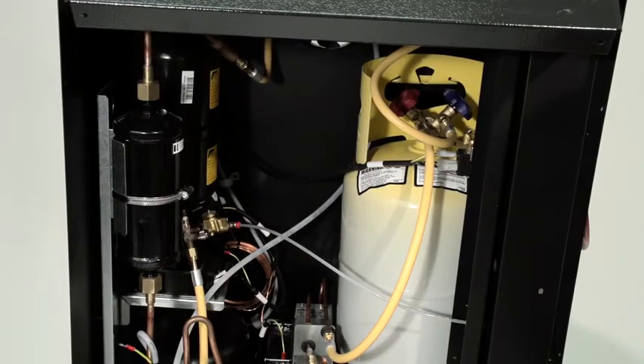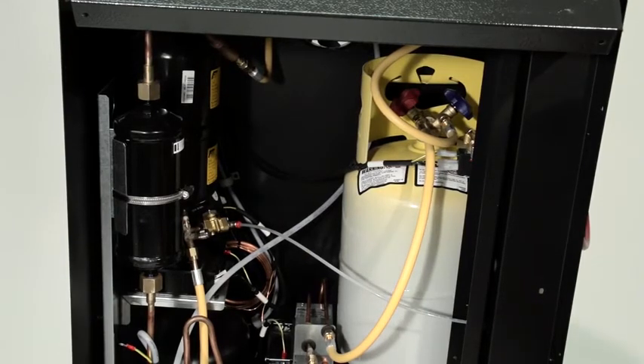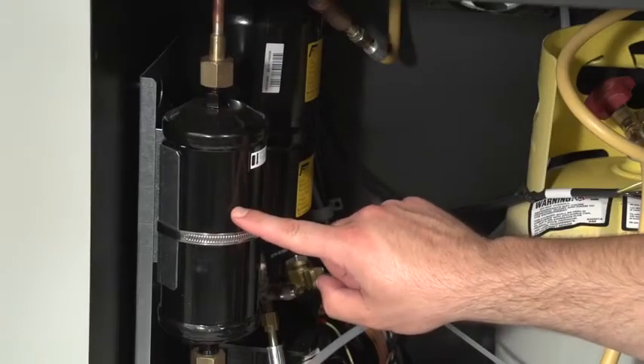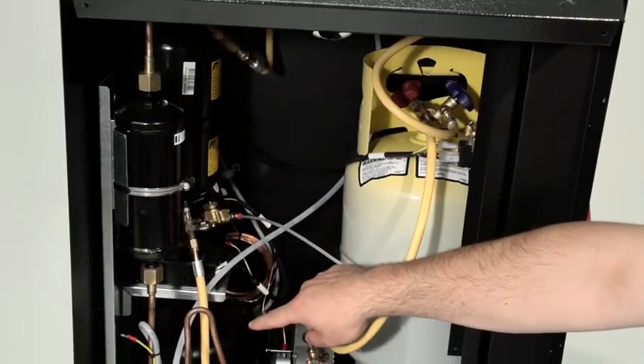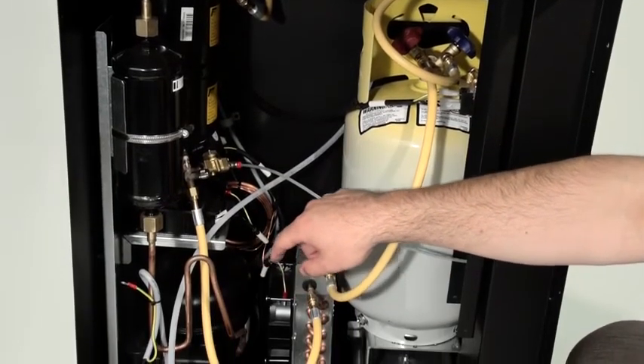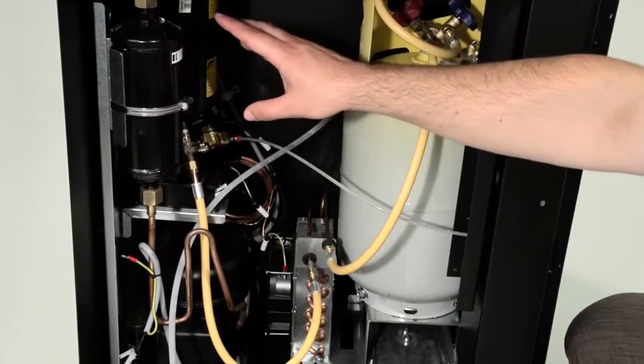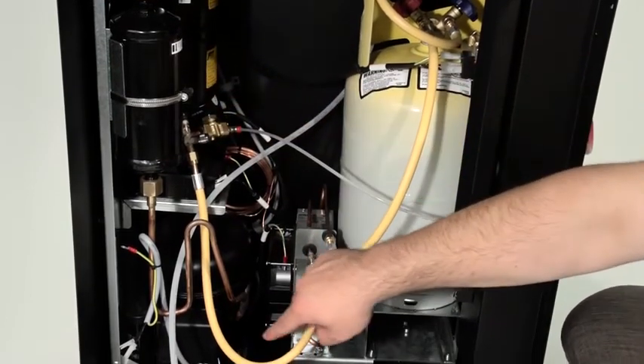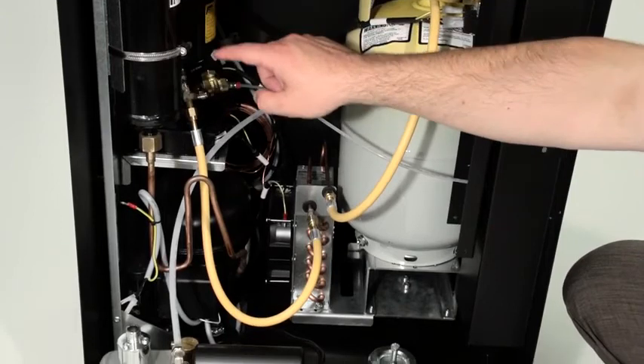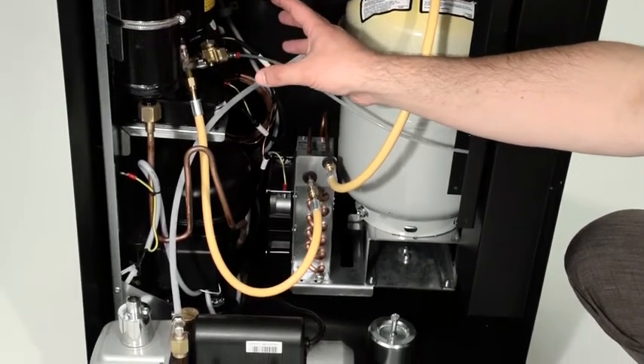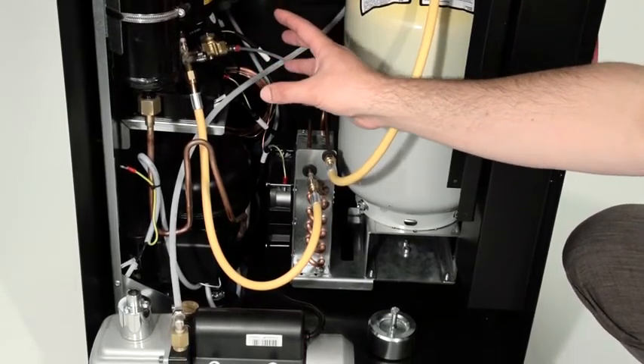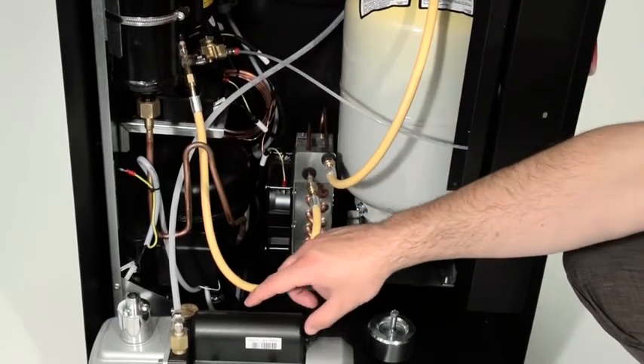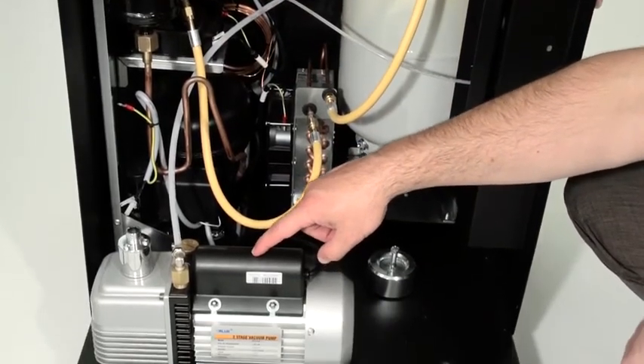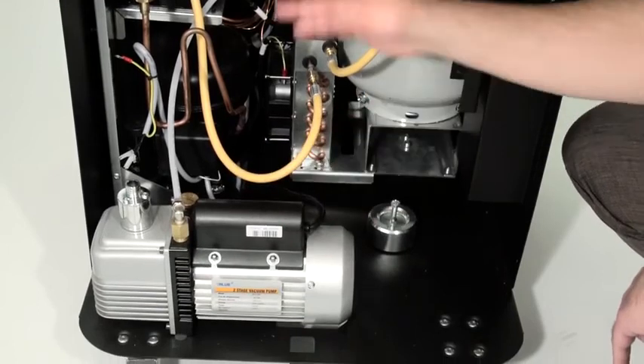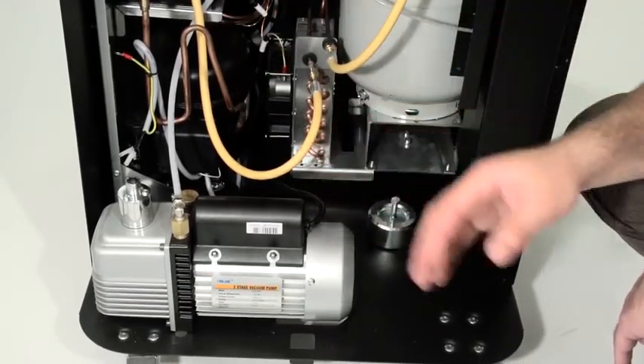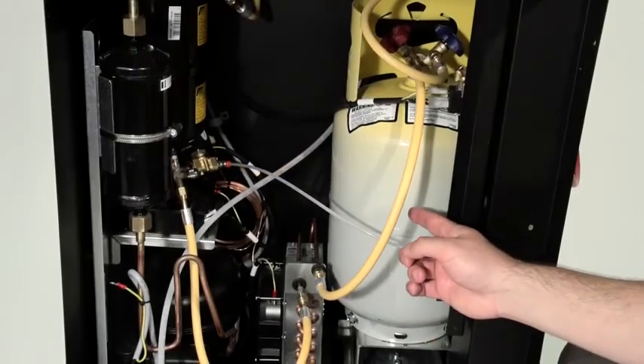Alright, so we're inside the front of the machine here. Here we have our filter dryer. Down here is our compressor. The compressor replacement will be this galvanized metal bracket here. We'll call it the compressor module. This is replaced as one unit. The vacuum pump down here in front will have to be moved out of the way to replace this compressor module. On this side of the machine we have our internal tank.